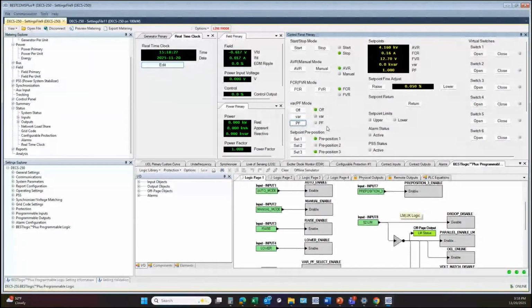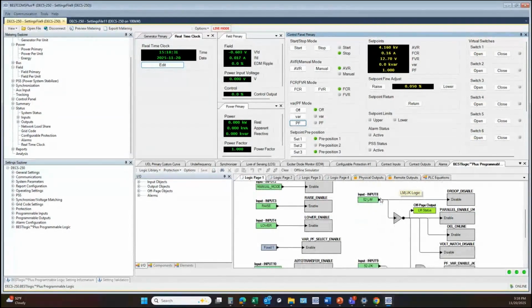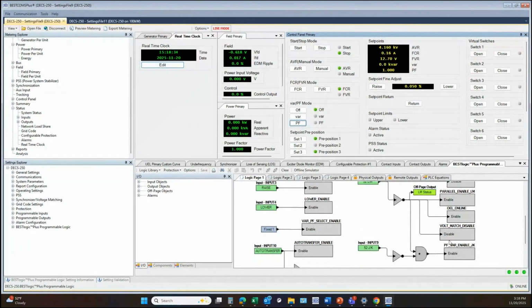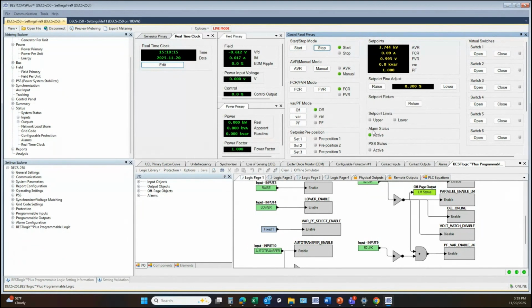And I cannot go into that mode of operation unless I'm meeting the logic conditions. So input 8 and 9 need to be false for this logic block to become enabled. I also need to be in a started state. I can't be tied to the utility grid if my DECS is not even in a started state. So if I give the DECS a start, okay, so the power factor actually changed. This indicator actually became active momentarily, but because my unit is not actually controlling a generator, it quickly ended up tripping off and went back to the off mode.